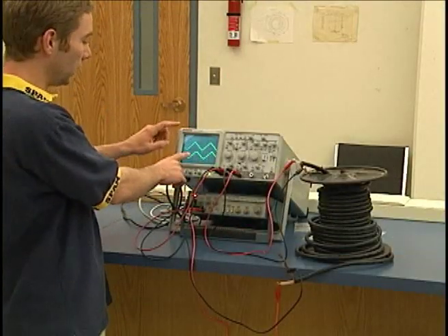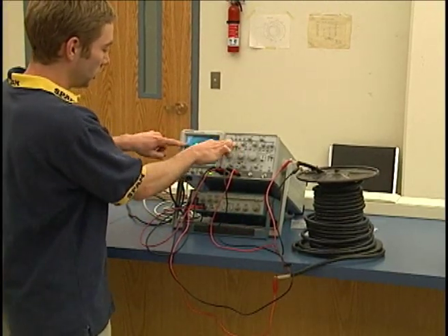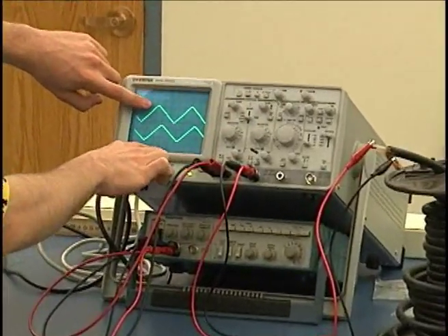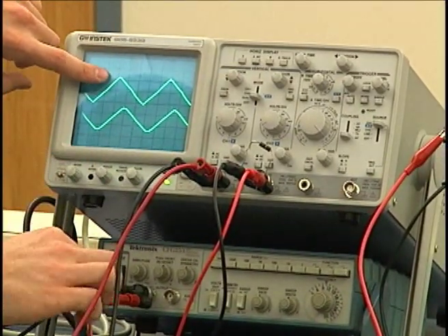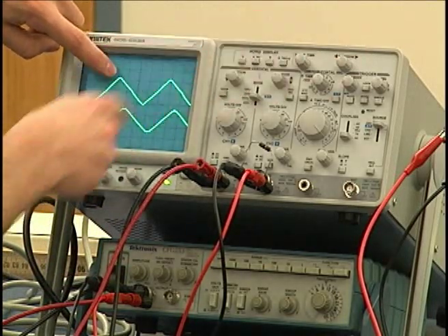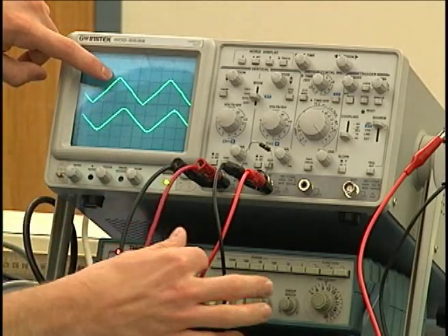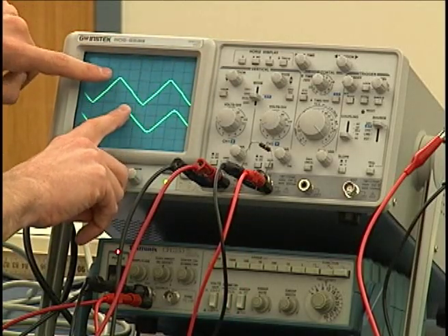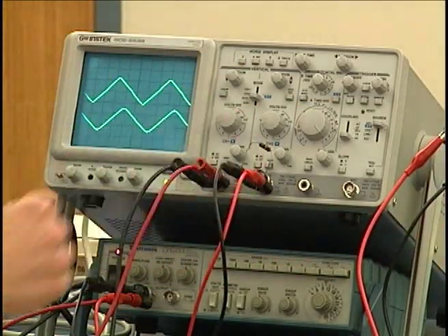So now that we have this, you can see right away that if I switch to channel 1, this is going to be channel 1 on top, channel 2 on the bottom. So if we look at both at the same time, you'll notice that this here's the original signal with peaks occurring here and here and so on down past where we can't see. And now we have this signal going through channel 2, going through all the cable, so that same peak is now going to be offset by a certain amount of time after traveling through this wire of a certain known length, which is written on the cable, or on the spool.